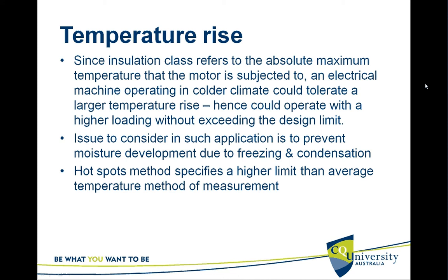Hotspots method specifies a higher limit than average temperature method of measurement. Nowadays most of these industries use thermal imaging techniques in order to find out what sort of hotspots are present in their electrical power network, and they sometimes get the thermal images of the electrical machines also.